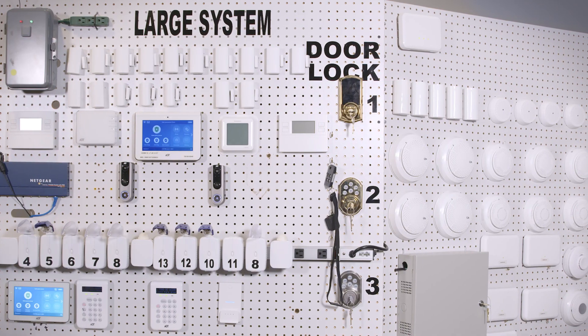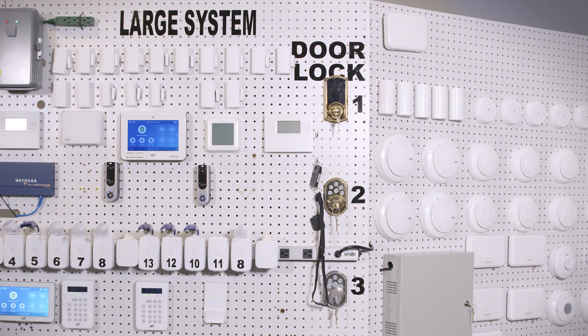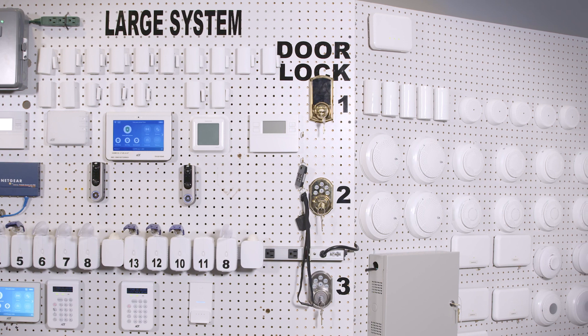We have some specifications or requirements for each of our panels that we launch. And so what you see here is actually 250 devices running schedules and alerts and events to ensure that the panel is going to function the same as it would with five zones, as it would with 128 zones.